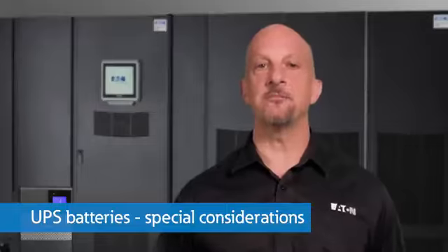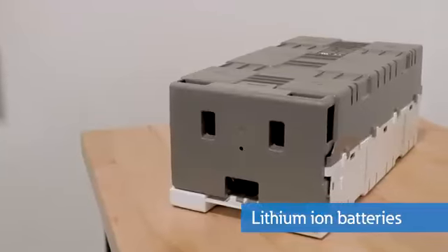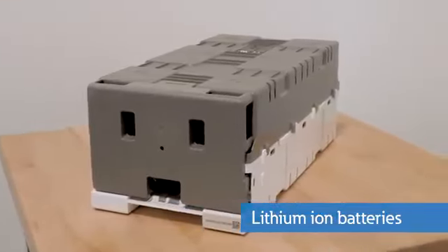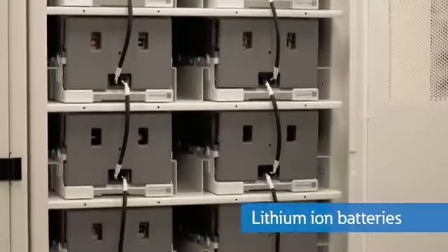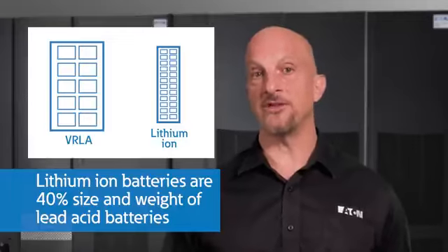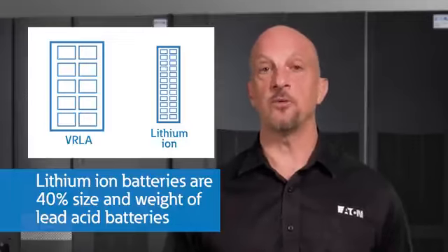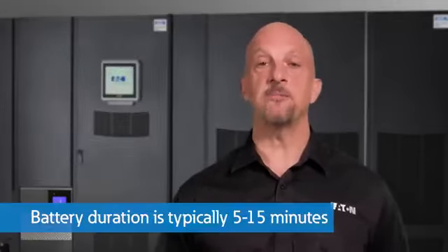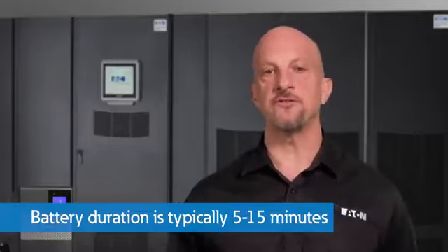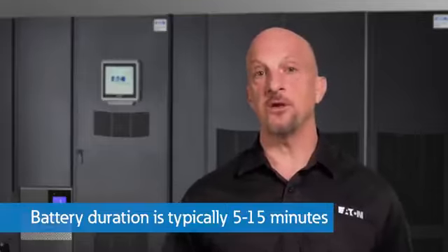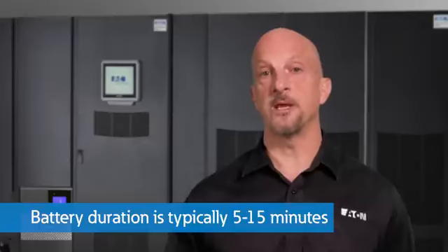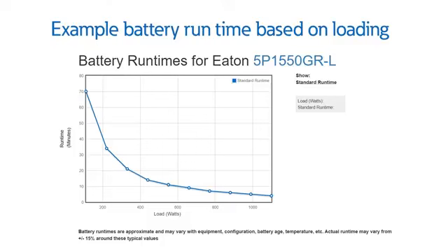Beyond the topologies, the battery systems that go with these UPSs have gone from traditional lead acid to much smaller, lighter, and longer life lithium-ion batteries. Therefore, today when you're shopping for a new UPS, it may be 40% of the size and weight of a previous model with the same electrical ratings and battery life. The duration of the battery runtime is usually in the range of 5 to 15 minutes, but it can be increased if more is needed. If the UPS is lightly loaded, you will get much more runtime out of the battery.